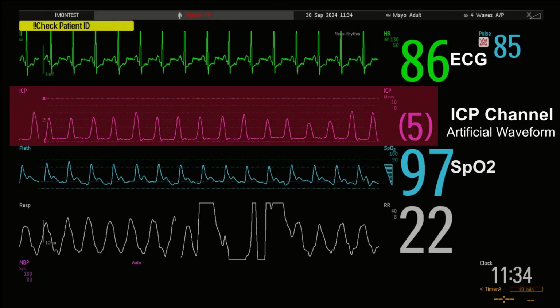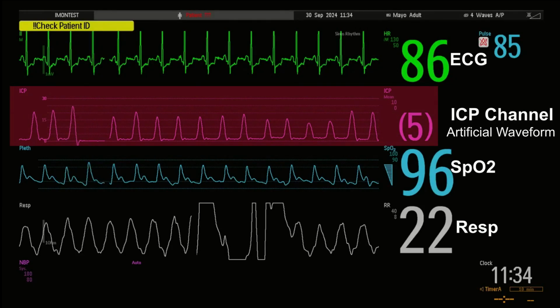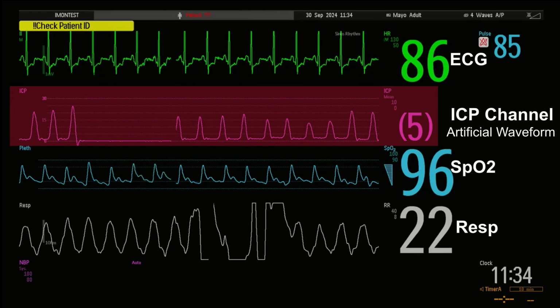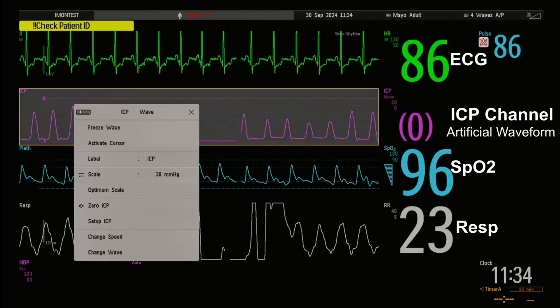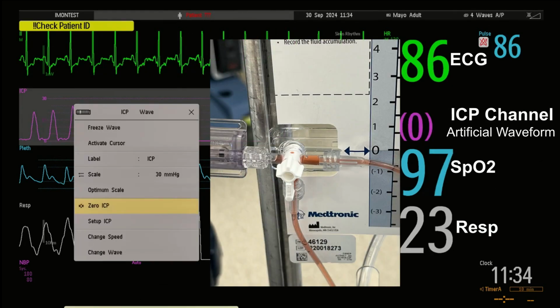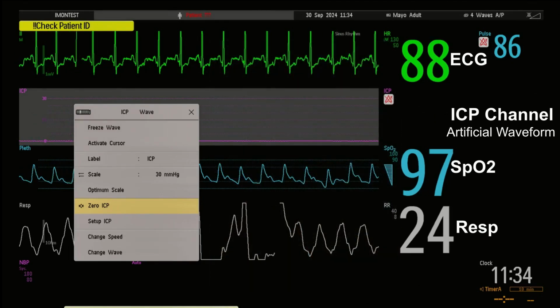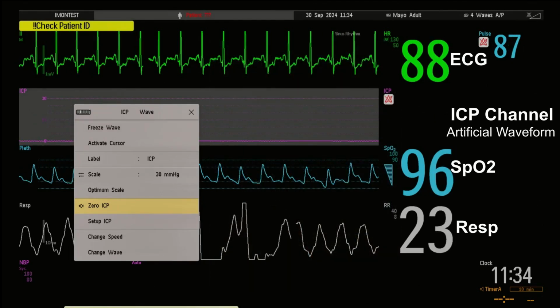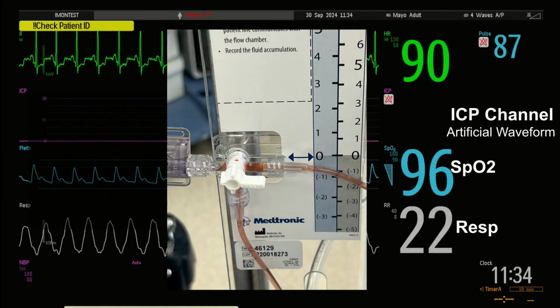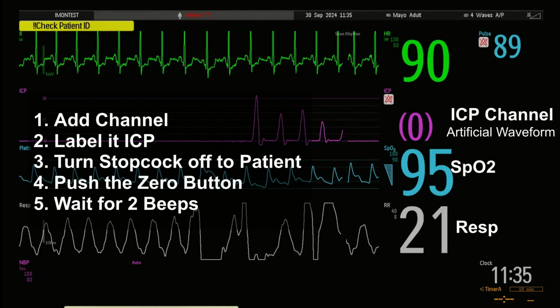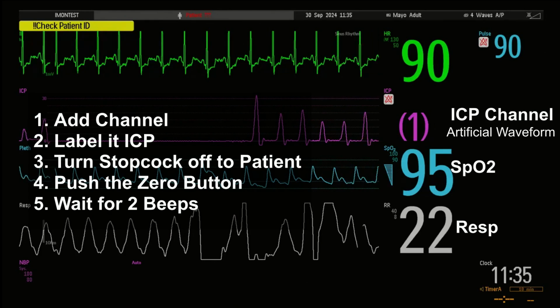Use the Philips monitor to set up one of the ports for ICP monitoring. You may need to change the label to ICP. With the stopcock turned off to the patient, push the 0 button on the monitor. You will hear 2 beeps come from the monitor when the zeroing process is complete. Now return the stopcock so that it is open to the transducer and closed to the drip chamber. You will now be able to view your zeroed waveform and an ICP measurement.